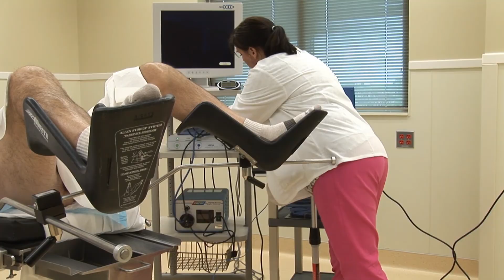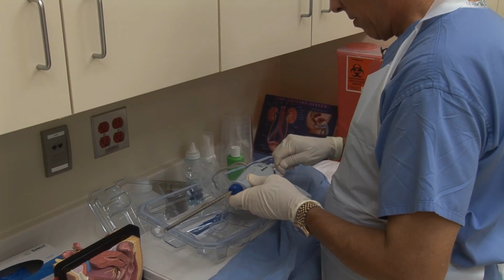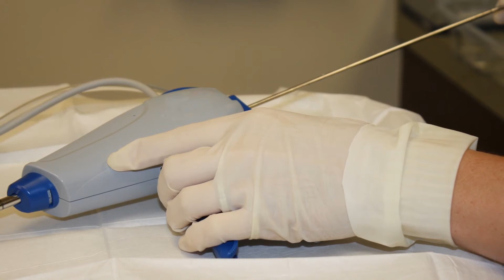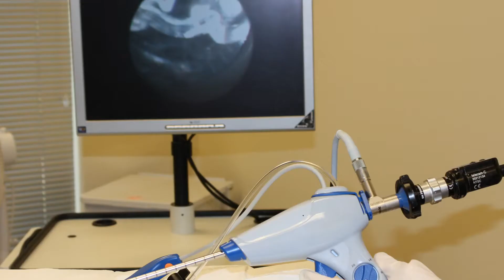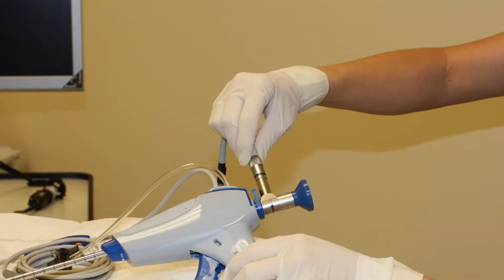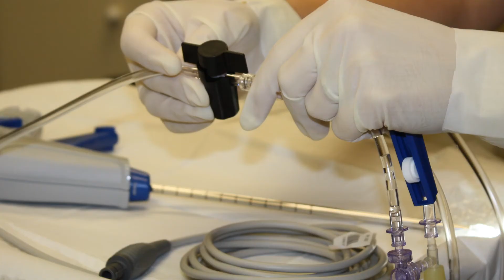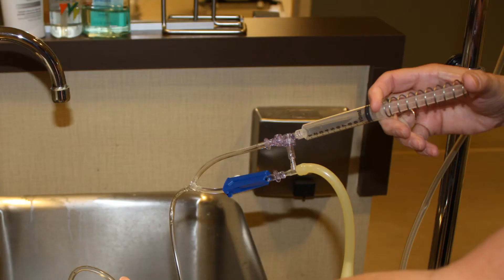The clinician must connect the telescope to the handpiece. It is best to hold it down distal on the telescope so it doesn't bend as it is pushed through. If difficulties with insertion are experienced, add water or lubrication to the shaft of the scope. Before beginning the procedure, confirm that it is locked into position. Assemble all pieces and connect the handpiece to the machine. Connect the light source and the water input and the camera. After the water is connected, run a small amount through to prime the tubing until there are no air bubbles in the tubing system.